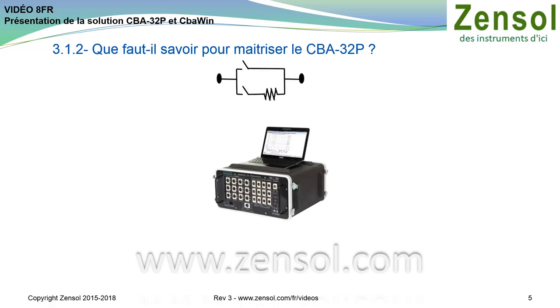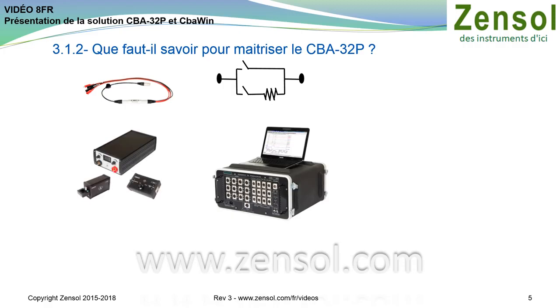The CBA-32P can store up to 24 main or auxiliary dry contacts, AC or DC currents up to 600 A, wet contacts up to 300 V AC or DC, AC or DC voltages up to 1500 V, linear or rotary displacements, and pressures.